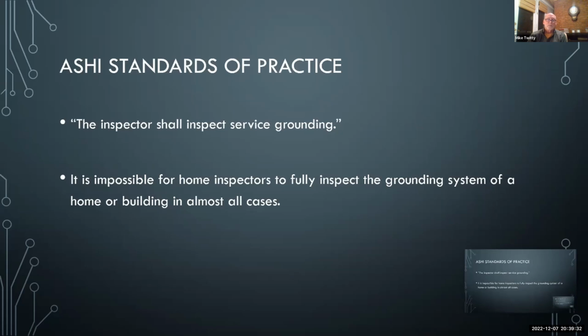So even home inspectors aside, I do some code compliance inspections, have in the past, and don't do many, but from time to time. And I did one last week for Metro Nashville, and the same situation. I couldn't confirm that the ground rod was 8 feet in the ground because it was a retrofit on an older house. They did drive a new ground rod, but I could see it, and it was properly clamped. Grounding electrode conductor was proper, so that's what I had to go on. So just keep that in mind. Don't put in your reports a statement that the grounding system is perfect and everything is right, because you really don't know that. So what do you do?